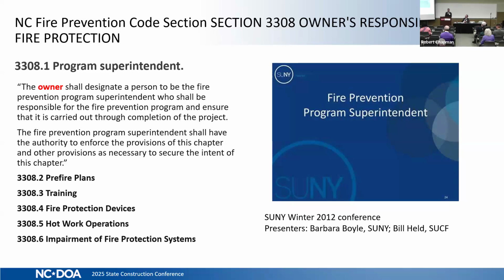Moving on, we have 3308.1, program superintendent. The owner shall designate a person to be the fire prevention program superintendent who shall be responsible for the fire prevention program. So this is the person that has to come up with the pre-fire plans. They make sure all the training's done, make sure the fire protection devices are set in their appropriate settings. And they're the ones that issue the hot work permits. Now if you've been to new construction, you know that this person is around. On every project, we know there's that individual.